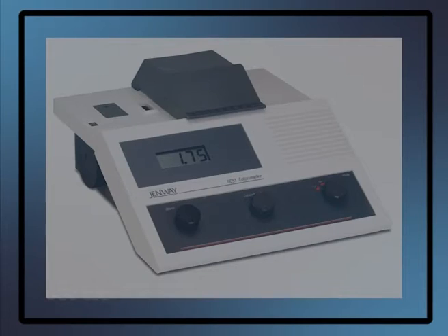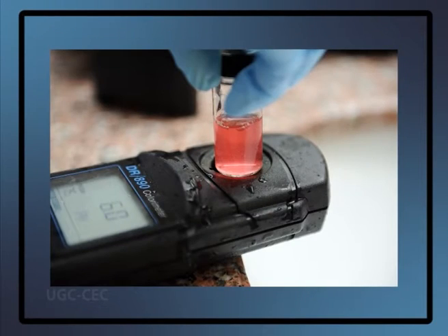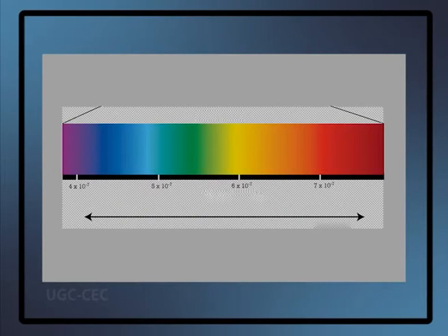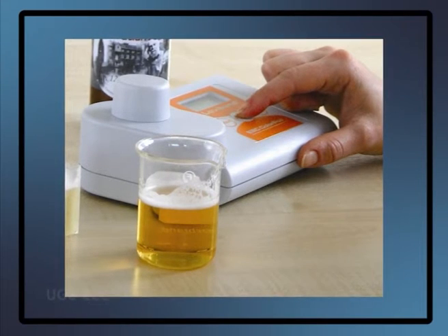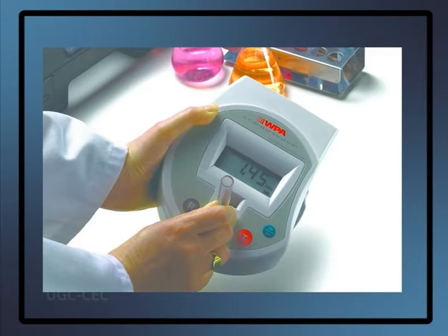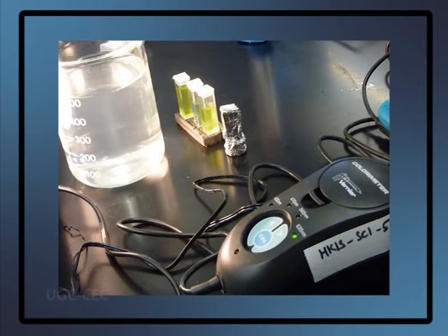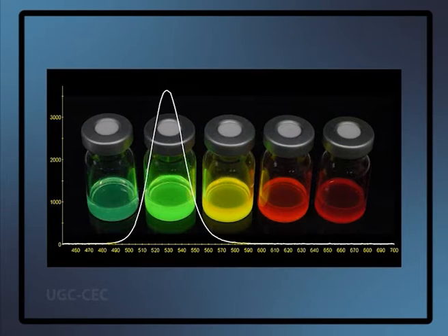Instrumentation. Colorimeter is any tool that characterizes color samples to provide an objective measure of color characteristics. Colorimeter allows the absorbance of a solution at a particular frequency of visible light to be determined. It relies on the principle that the absorbance of a substance is proportional to its concentration. Filter in the colorimeter is used to select the color of light which the solute absorbs the most in order to maximize the accuracy. Sensors measure the amount of light which has passed through the solution compared to the amount entering, and a display reads the amount absorbed.